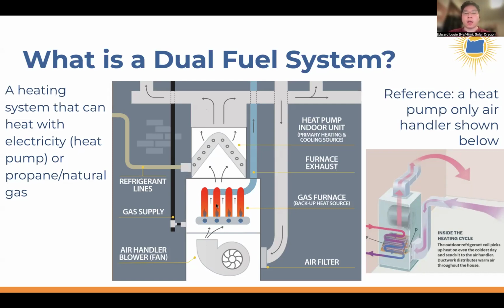You cannot have both of them running at the same time. You can imagine how problematic that would be. You would have very hot air being produced by this gas heat exchanger, and then that super hot air would cook the coil so hot that the refrigerant in the coil would not work properly. And so there's controls in a dual fuel heat pump so that you can never operate both at the same time.